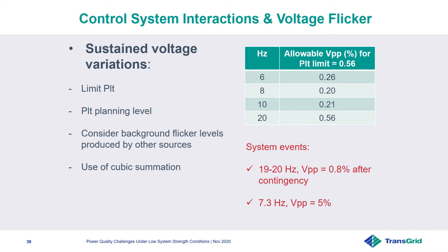So our approach is to determine a limit for oscillation magnitudes based on its impact on PLT, the long-term flicker index. The considerations are the PLT planning level, background flicker levels produced by other sources, and use of the cubic summation law. Then we have established allowable oscillation magnitudes from control system interactions for a specific location, as given in the table here as an example. You can see that these levels are quite small and depend on the modulation frequency.